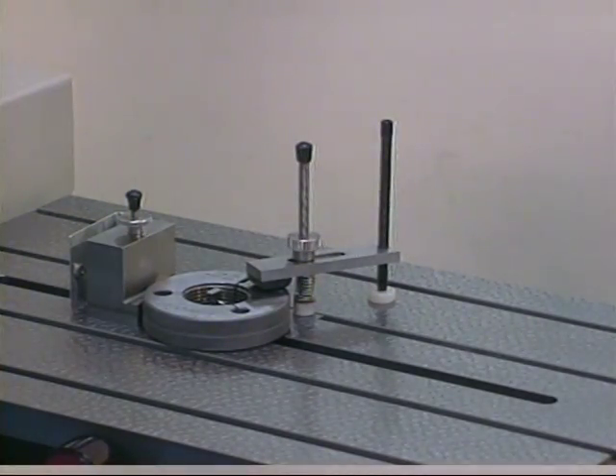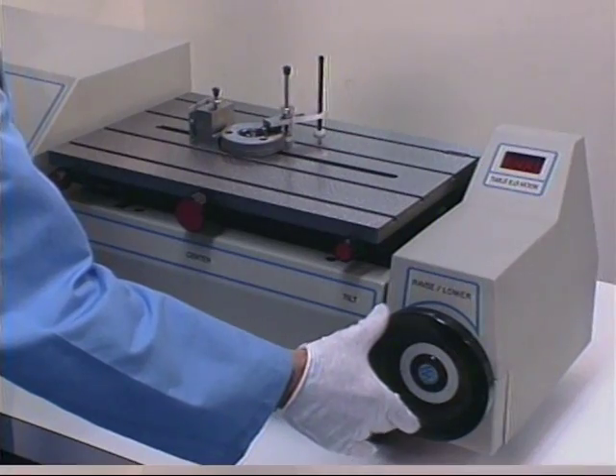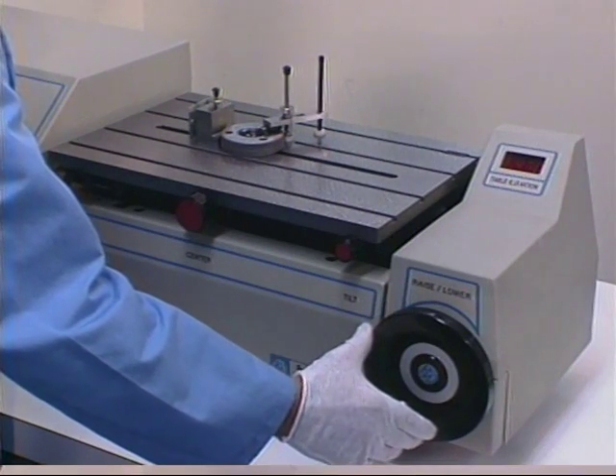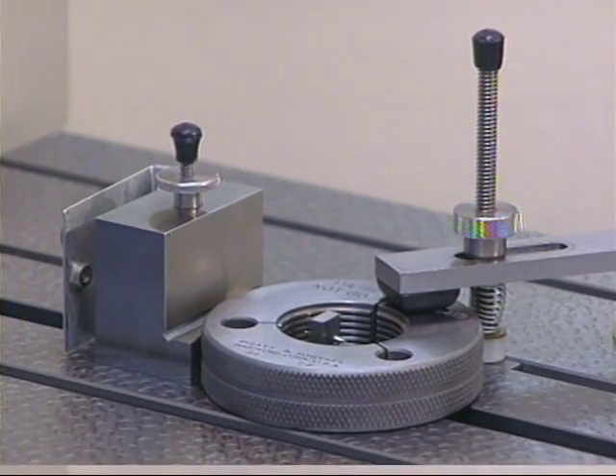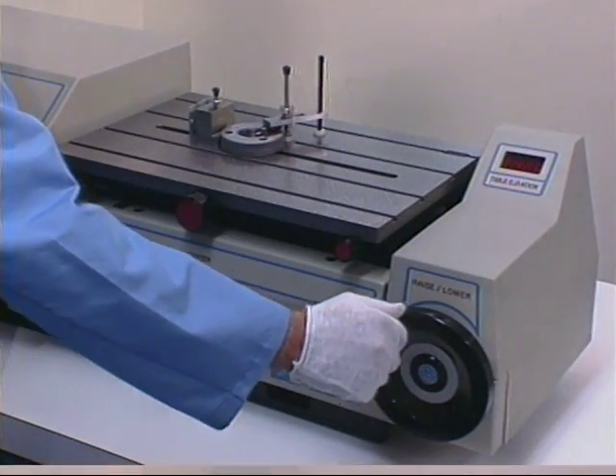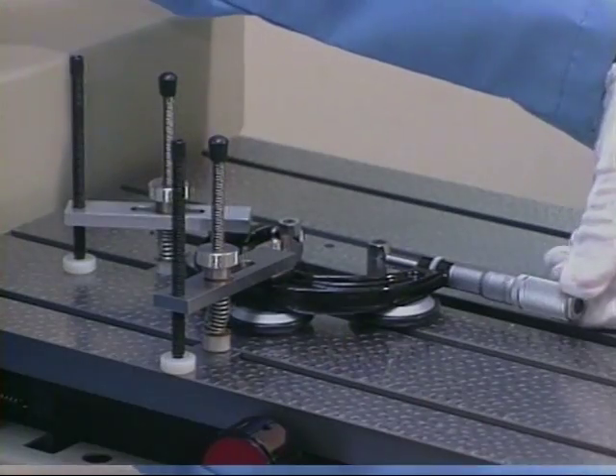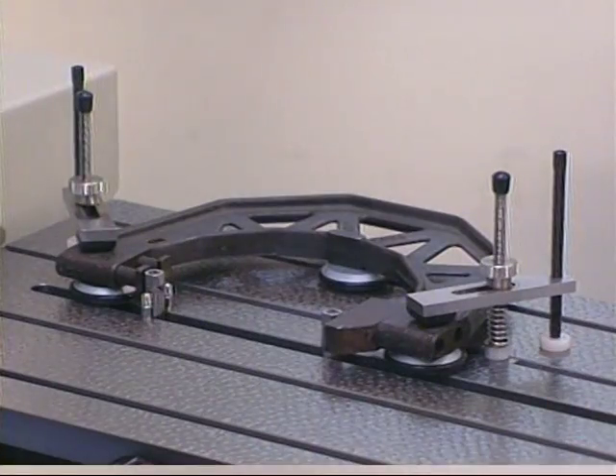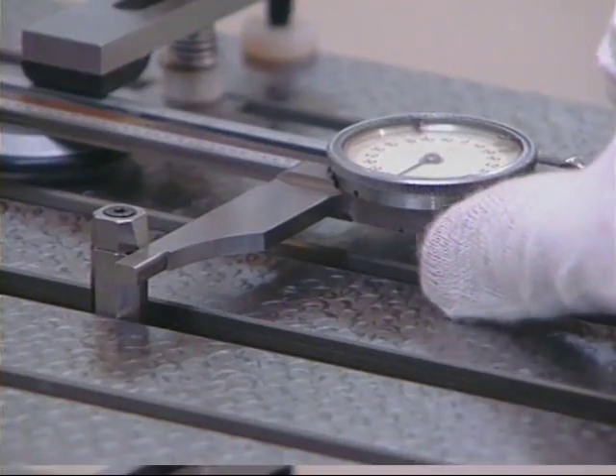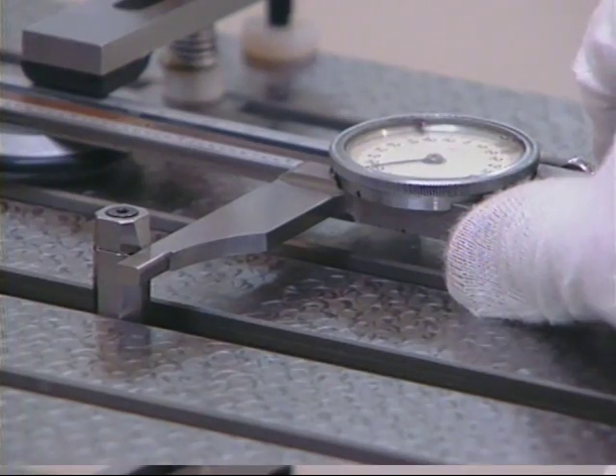and move the probe over to the left side. We search for a minimum reading using the centering and table elevation adjustments. Once established, we set 0. Bring the probe to the opposite side to find the maximum reading by raising and lowering the table. The measurement of micrometers, snap gauges, and calipers is easily carried out with the aid of optional accessories.